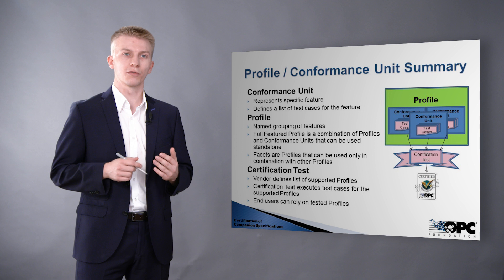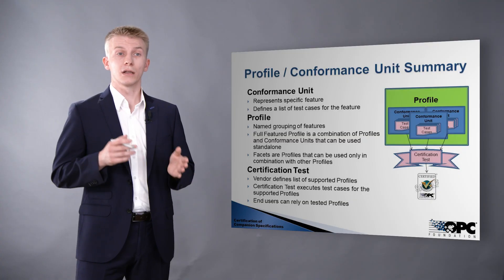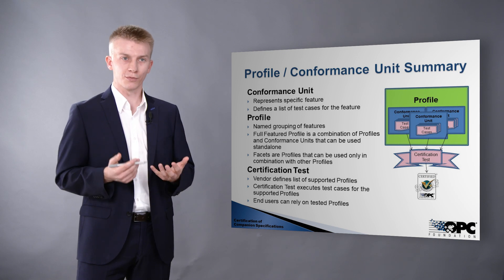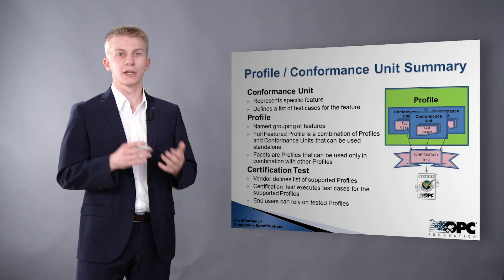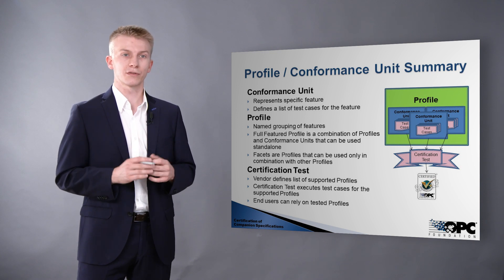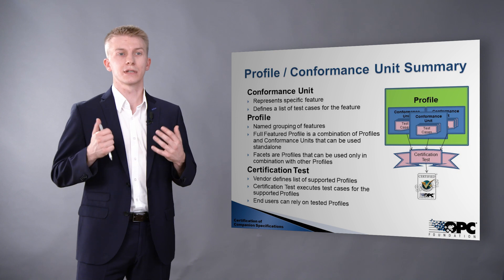To recap: a conformance unit is the smallest testable item, representing a specific feature, and defines a list of test cases mapped to that feature. A profile has a name grouping several features. A full featured profile is a combination of profiles and conformance units to have a standalone server, while a facet can't stand by itself. In certification testing, the vendor defines which profiles the product supports, and certification testing verifies those profiles are correctly implemented by executing the test cases. All profiles that the implementation successfully passes are written on the certificate, so end users can trust the tested profiles.